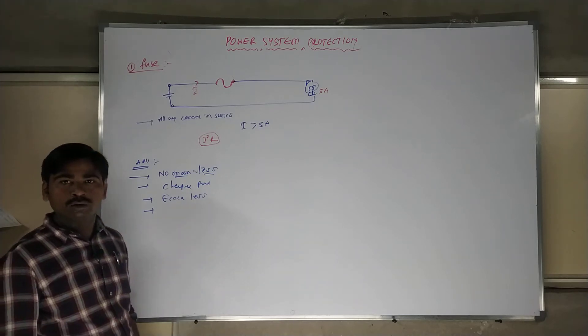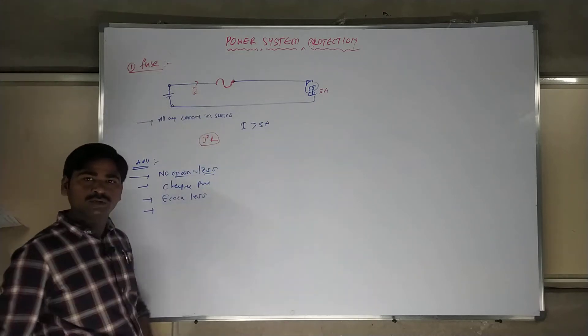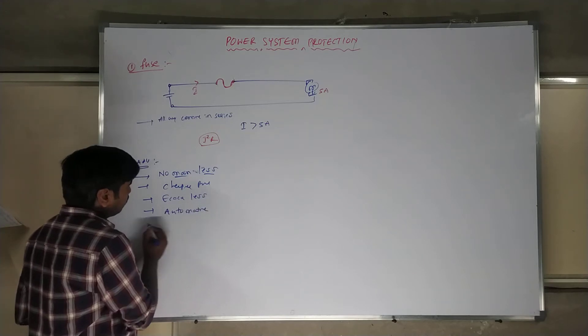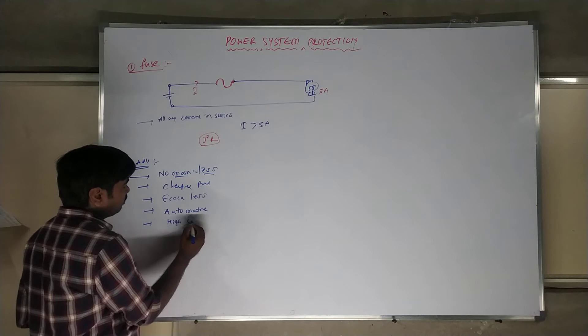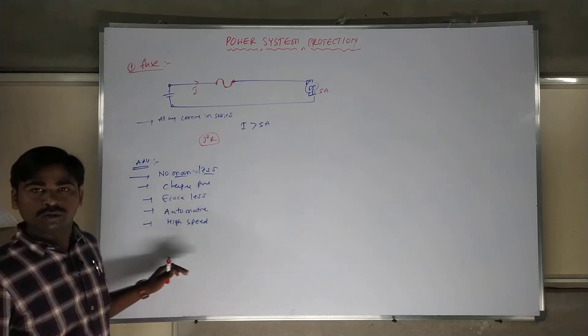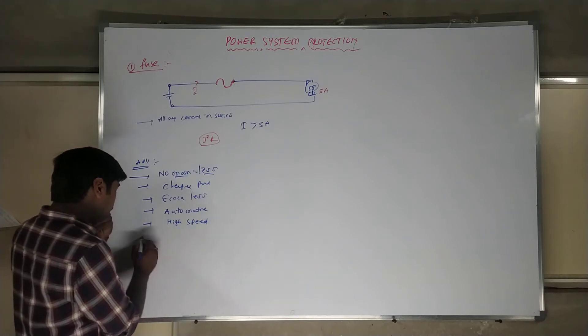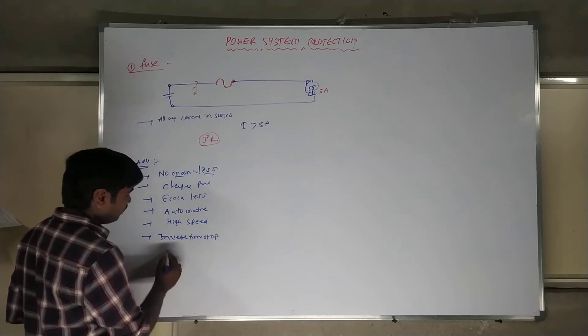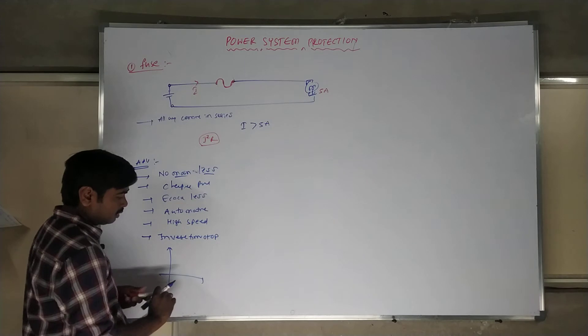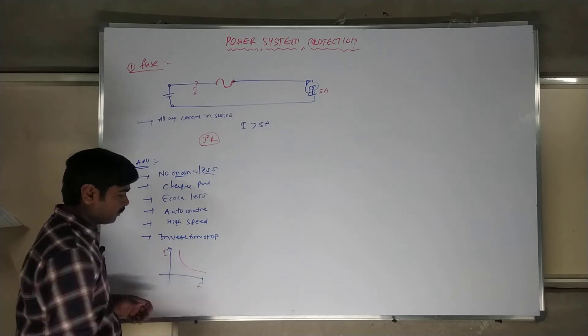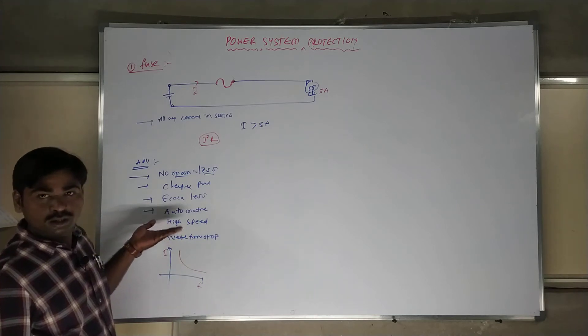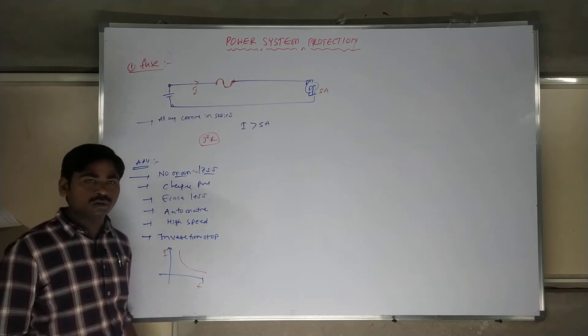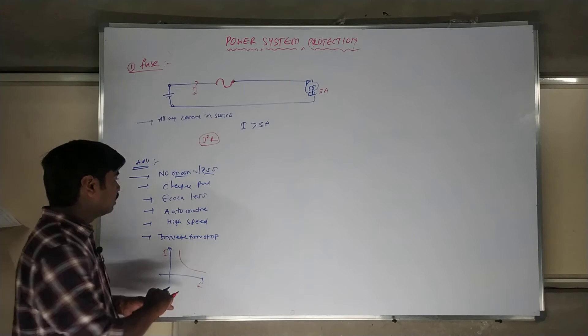One more thing is the operation is automatic — no one needs to come and open the fuse; it will automatically melt. The operation is automatic and also high speed. Excess current will cause it to open very quickly. It also has an inverse time characteristic: when you draw a current-time diagram, it is inversely related — when current increases, time decreases. Excess current will cause the fuse to open in the shortest span of time. That is the inverse time characteristic, which is very advantageous.